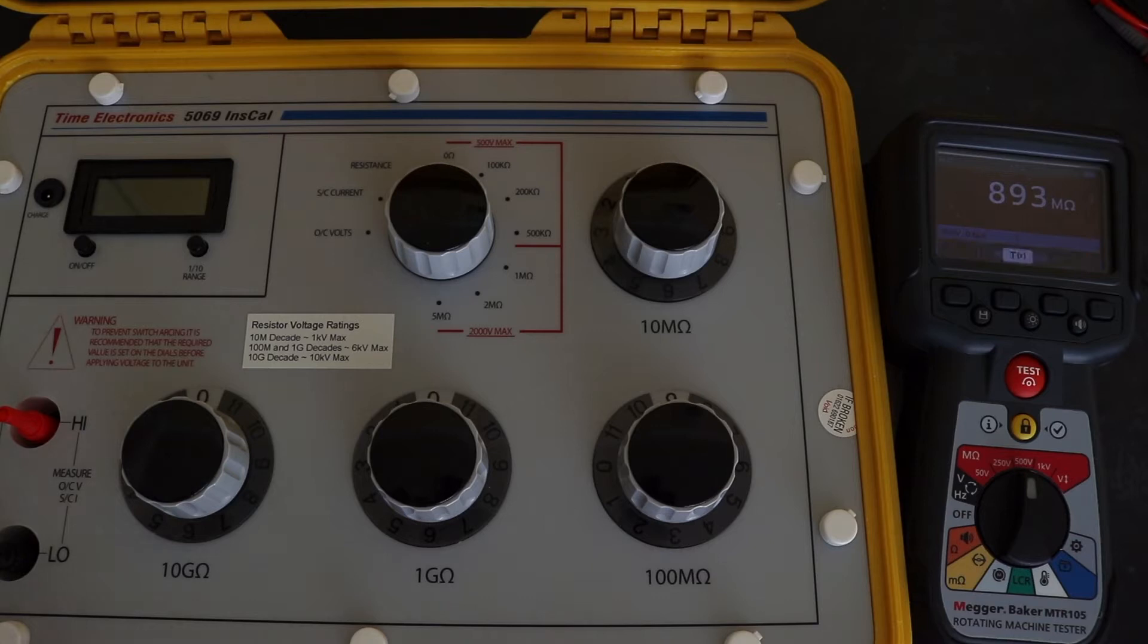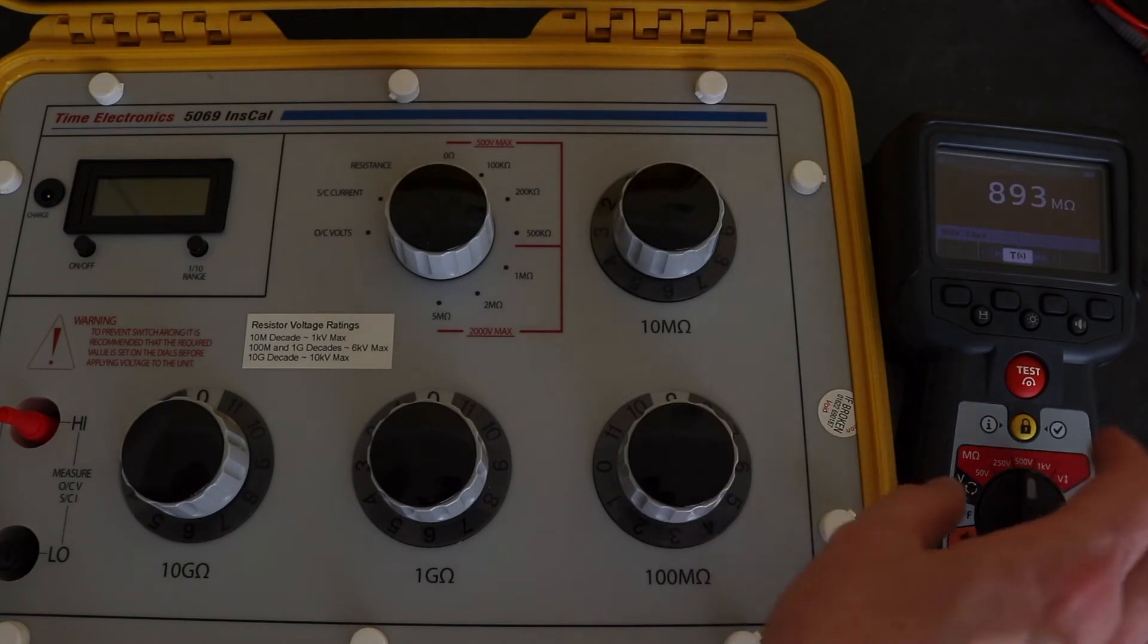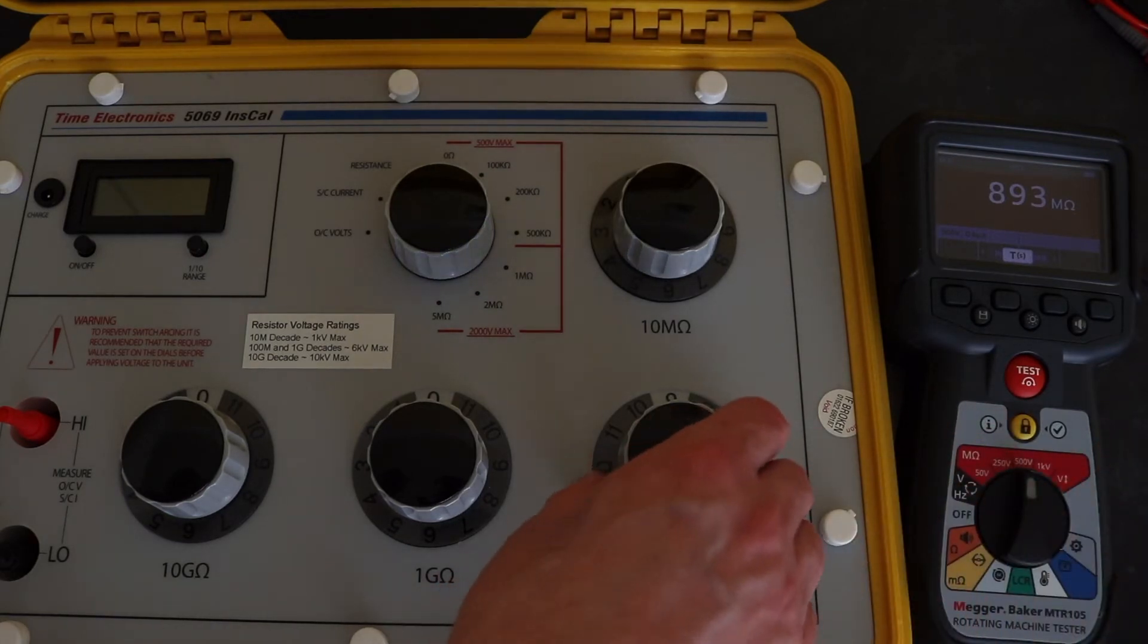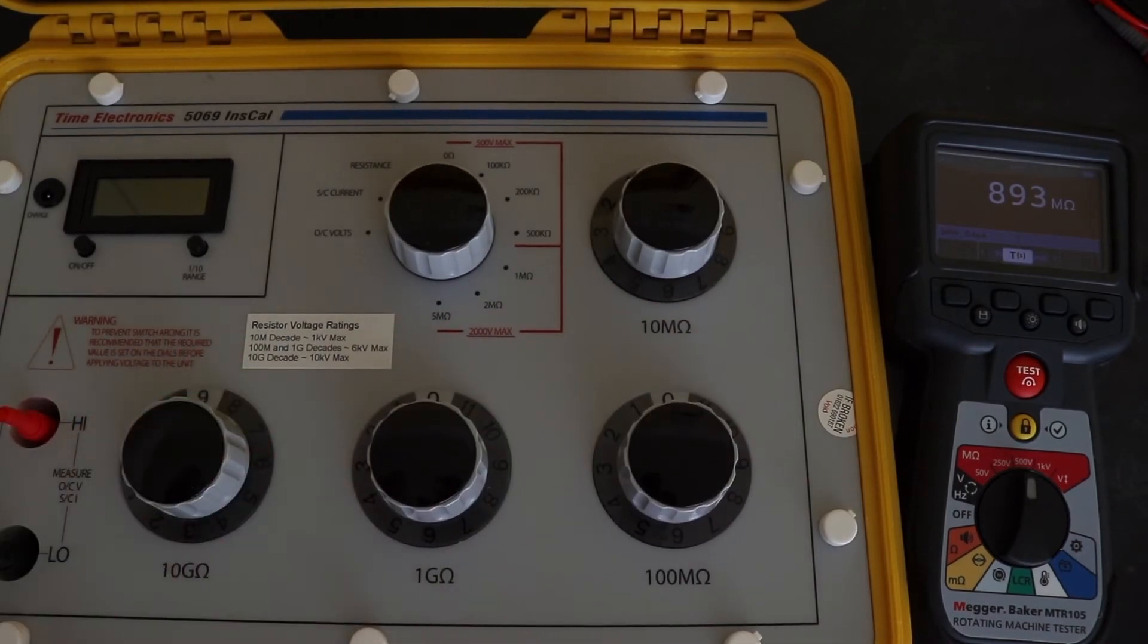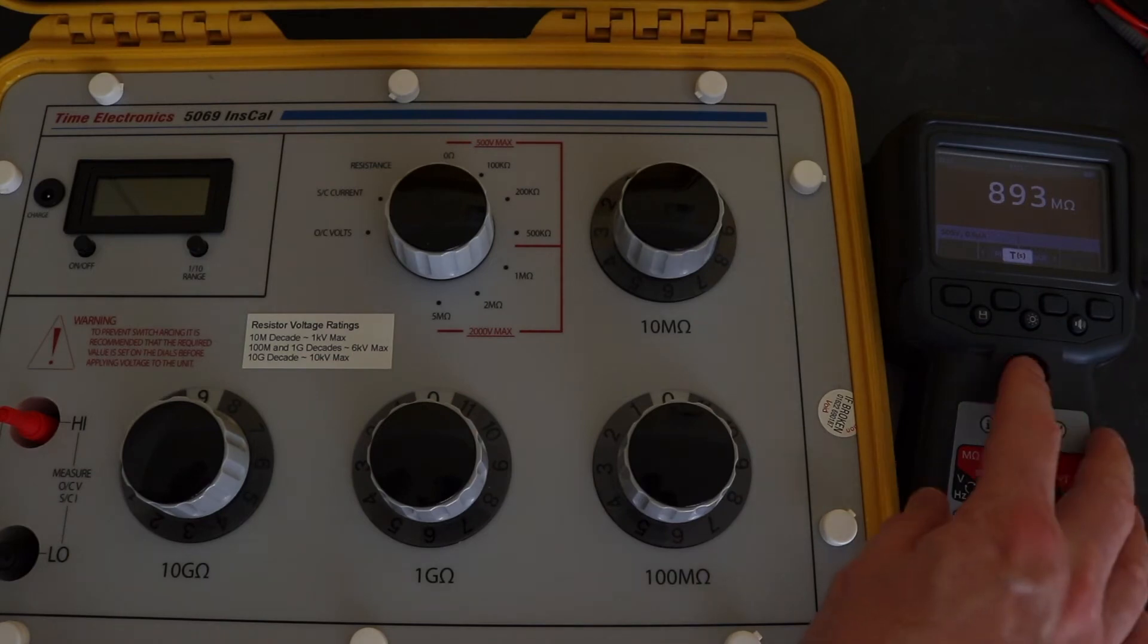So you find that happens when you get into the high 100 meg, 1 gig ohms and 10 gig ohms ranges on the decade box. What I will do is I will set this up for a 500 volt test for one minute at 90 giga ohms and we'll see what value it comes back with. I'll then do the same test using the U1461A.